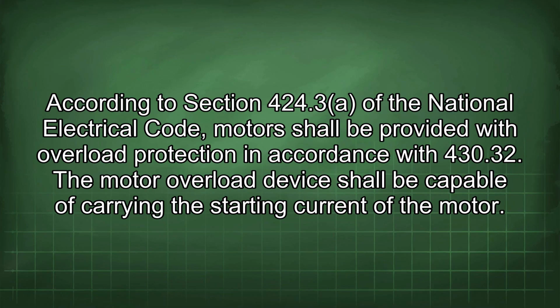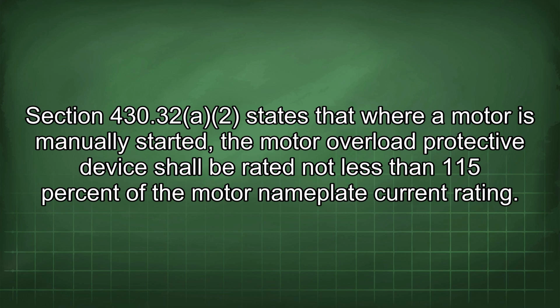According to Section 424.3 of the National Electrical Code, motors shall be provided with overload protection in accordance with 430.32. The motor overload device shall be capable of carrying the starting current of the motor. Section 430.32 states that where a motor is manually started, the motor overload protective device shall be rated not less than 115% of the motor nameplate current rating.